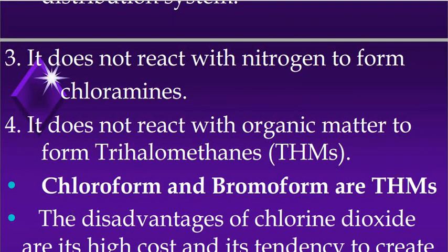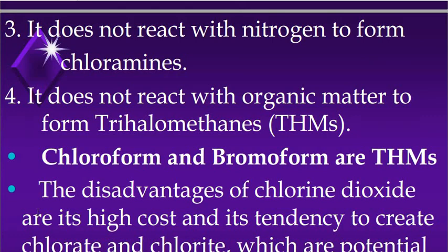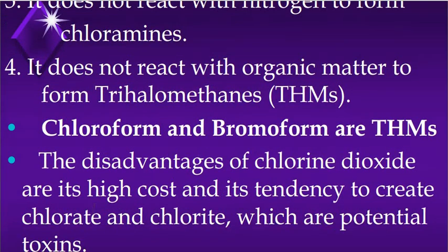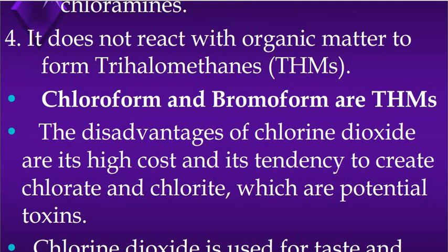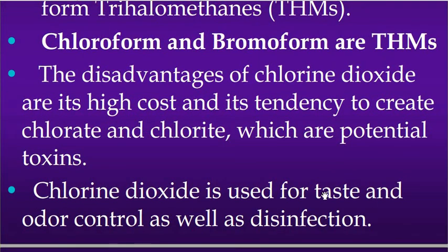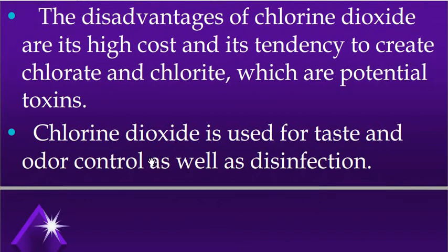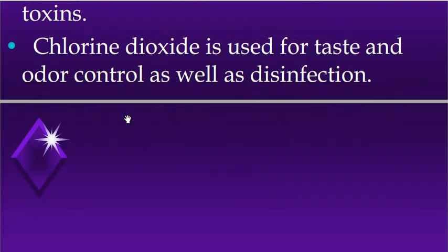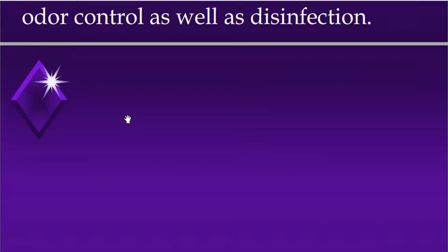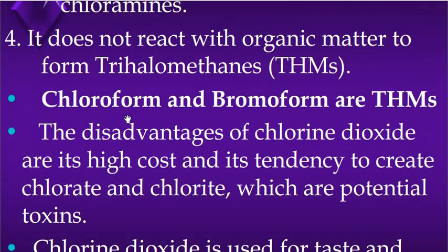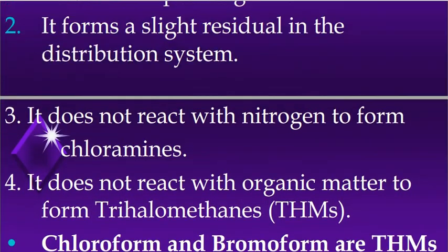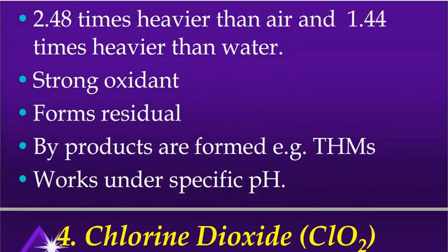So the disadvantages of chlorine dioxide are its high cost and its tendency to create chlorate and chlorite, which are potential toxins. Chlorine dioxide is used for taste and odor control as well as for disinfection. So these are the generally used applications of the chlorine we have discussed.